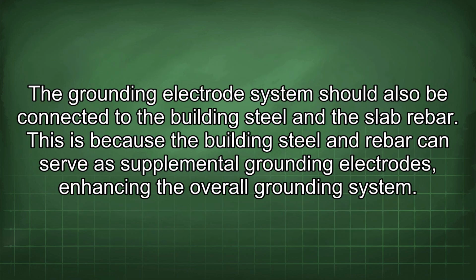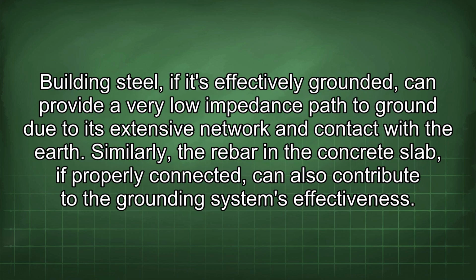The grounding electrode system should also be connected to the building steel and the slab rebar. This is because the building steel and rebar can serve as supplemental grounding electrodes, enhancing the overall grounding system. Building steel, if it's effectively grounded, can provide a very low impedance path to ground due to its extensive network and contact with the earth. Similarly, the rebar in the concrete slab, if properly connected, can also contribute to the grounding system's effectiveness.